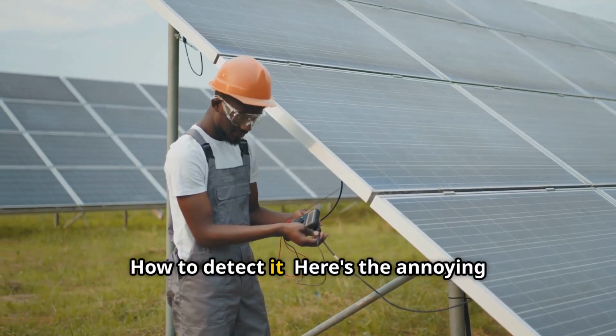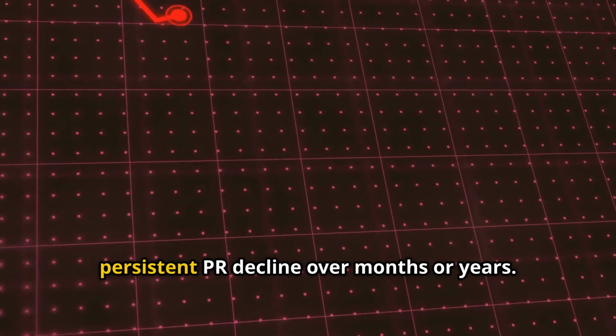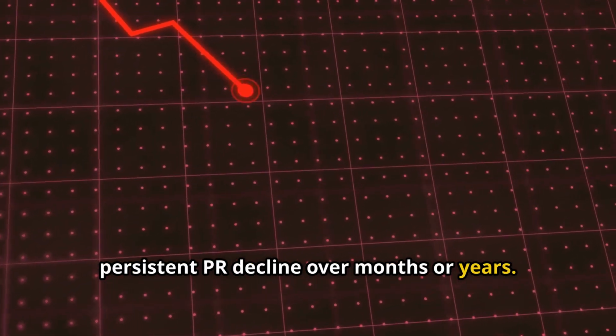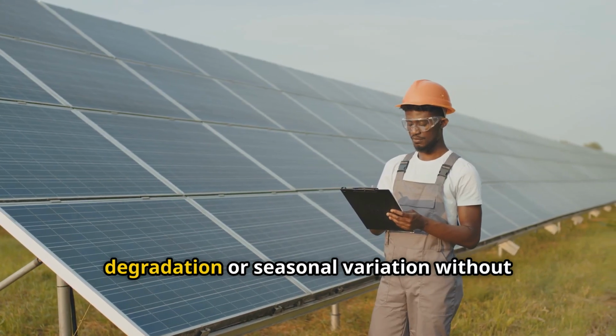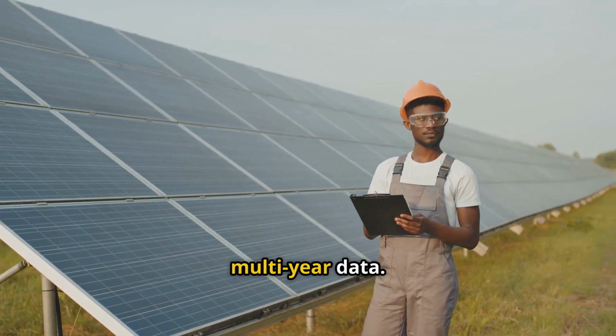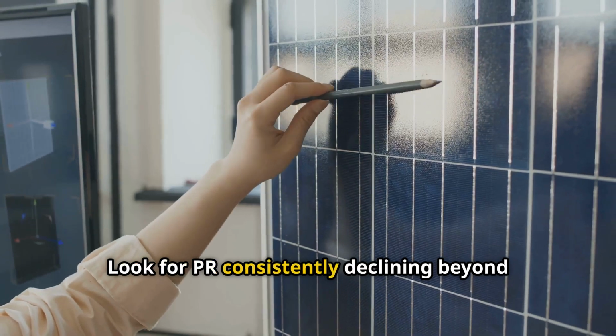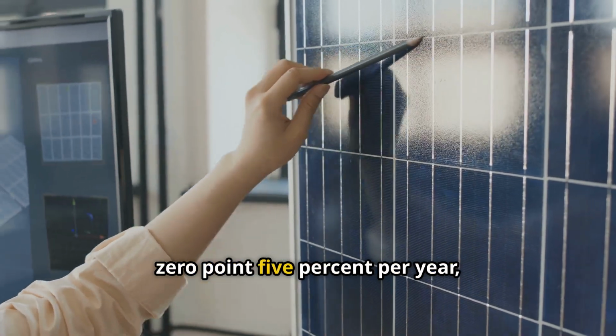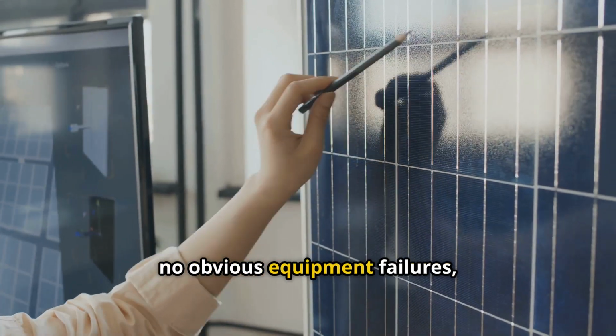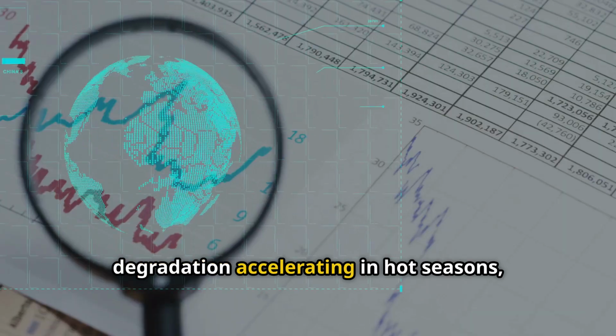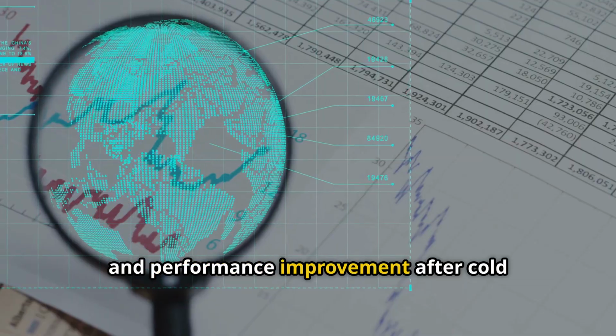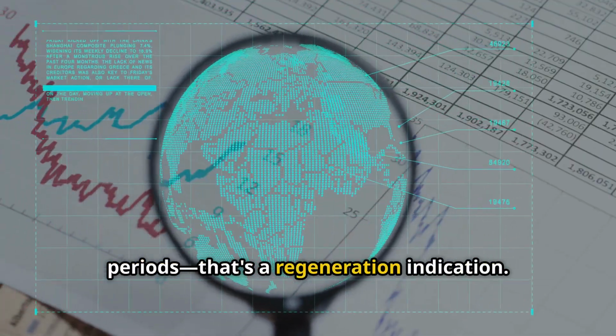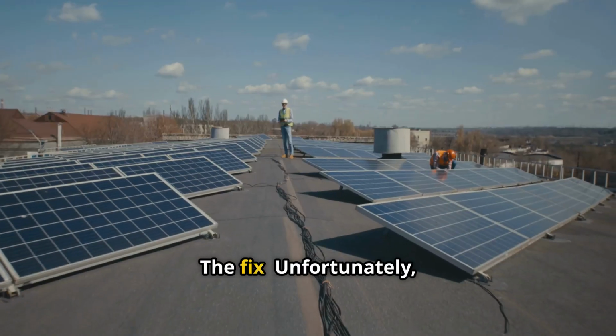How to detect it? Here's the annoying part. LETID shows as gradual, persistent PR decline over months or years. It's hard to distinguish from normal degradation or seasonal variation without multi-year data. Look for PR consistently declining beyond 0.5% per year, no obvious equipment failures, degradation accelerating in hot seasons, and performance improvement after cold periods. That's a regeneration indication.